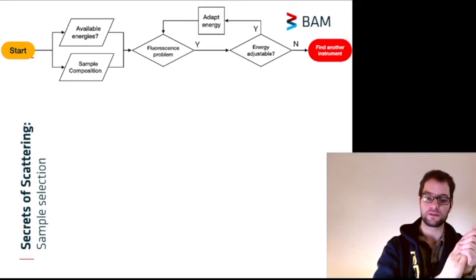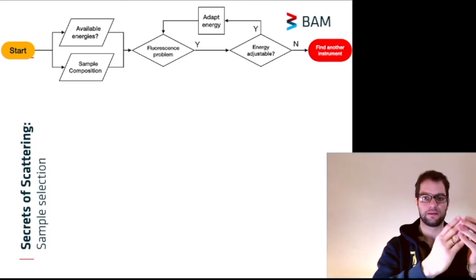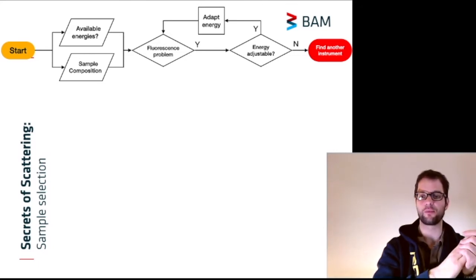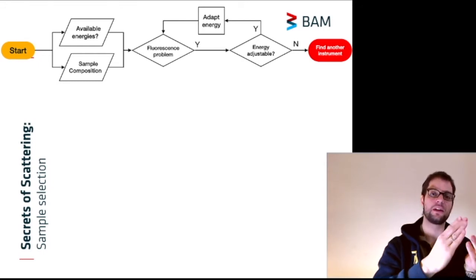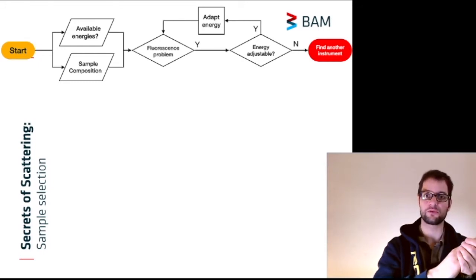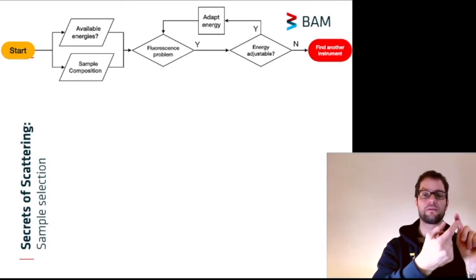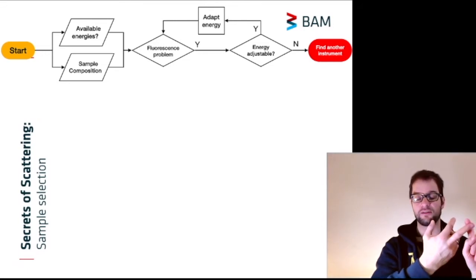So, if you've looked at your sample composition and you think this might be a problem, try to find out if you can adjust the energy. In our laboratory instrument, we have two energies available. We have copper energy, which is the most intense source that we have, but we also have molybdenum energy available.